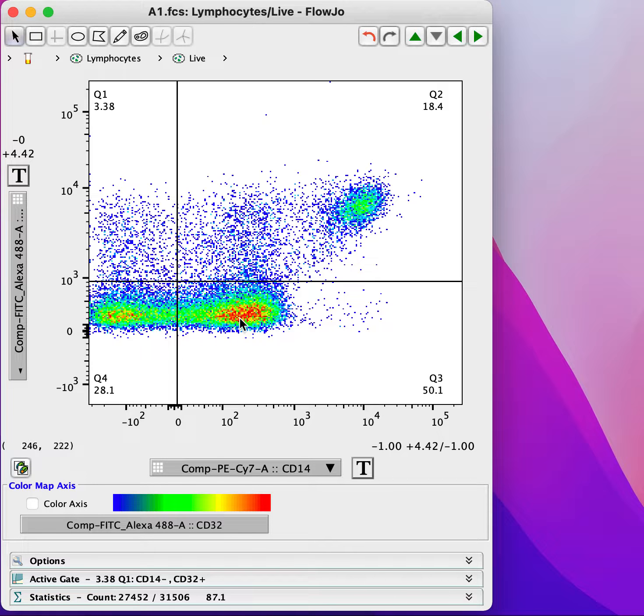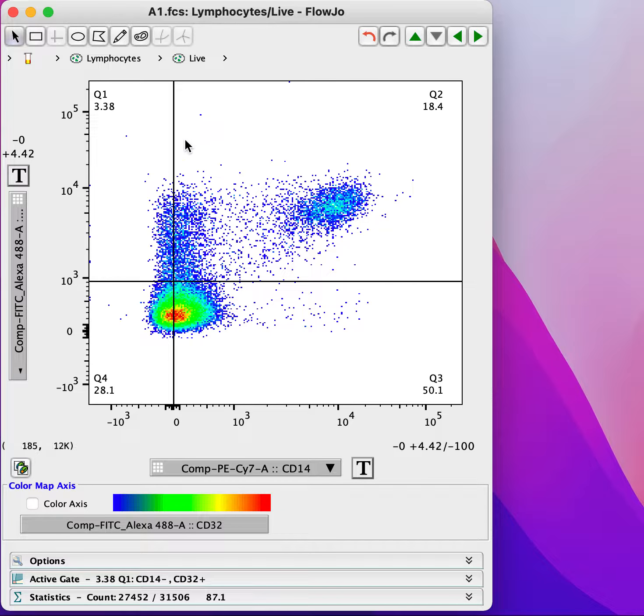That should send up a warning, because you would not expect a flow cytometer to have any kind of resolution at this level of the scale. This is the area where the differences in signal are just dominated by noise and random fluctuation. Let's reset the scale and see how our gate looks. And you can see that where we placed the gate just bisects this population.